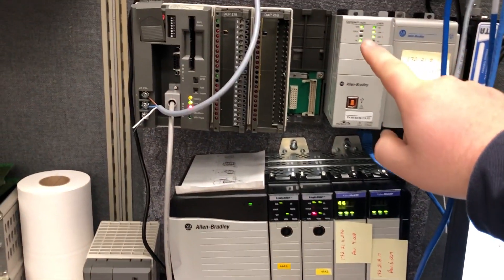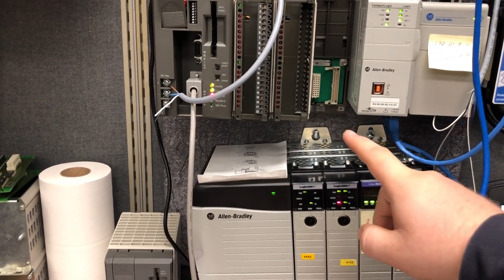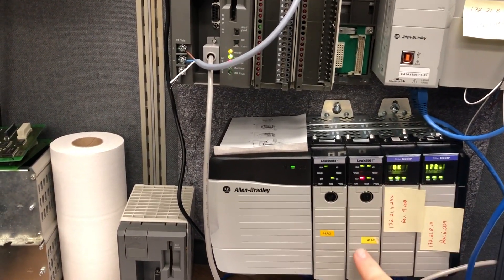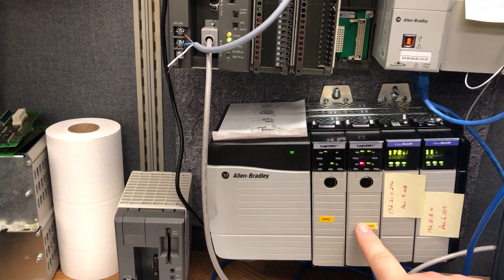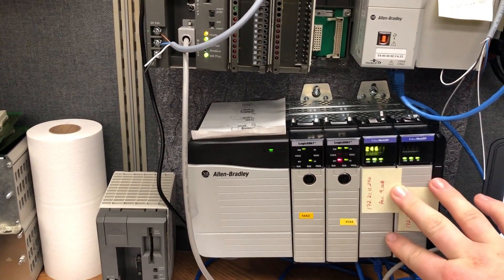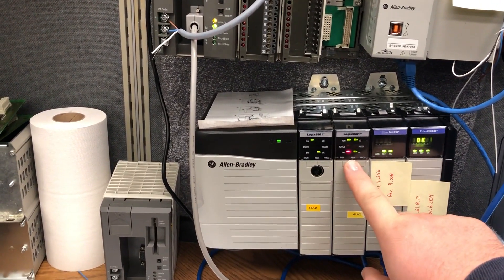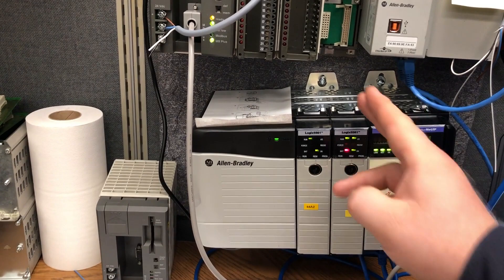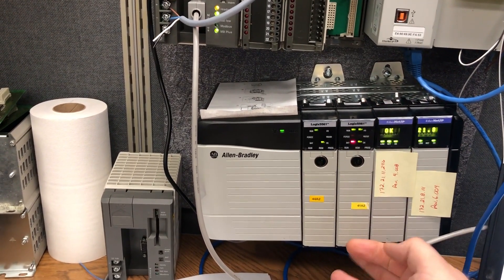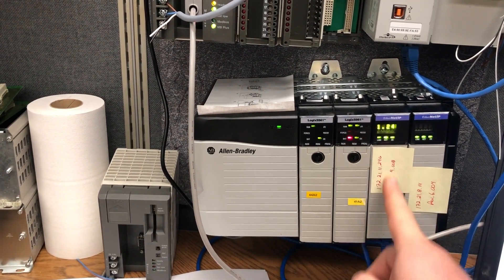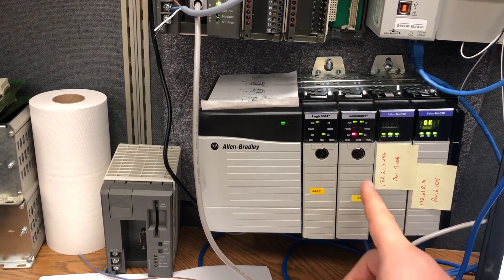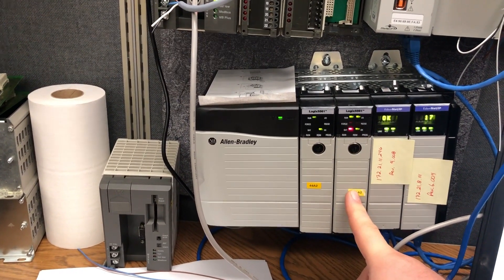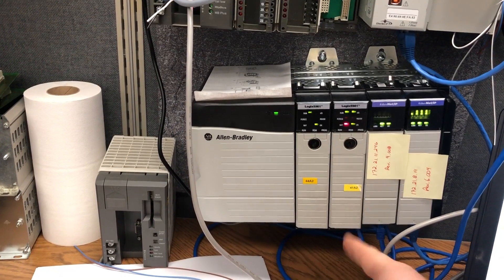From this PLC which is in slot one of this backplane, it's a Control Logix L61, but it does not have Ethernet. It uses an ENBT card like the old style. Some of the newer ones like the L83s have Ethernet in the controller themselves and they don't need an ENBT type card, an Ethernet adapter.